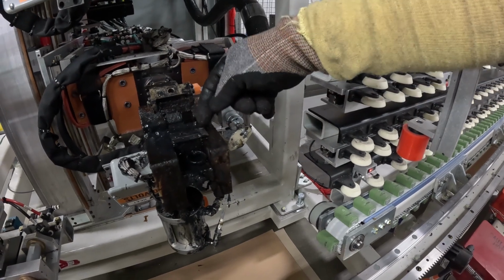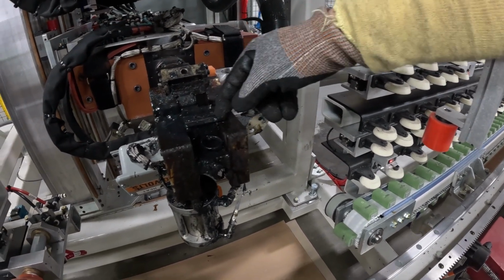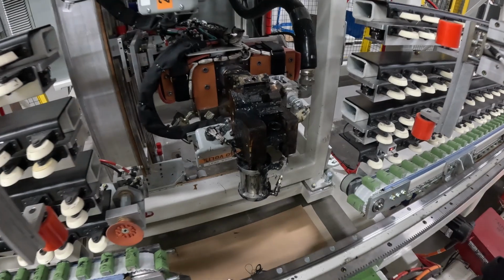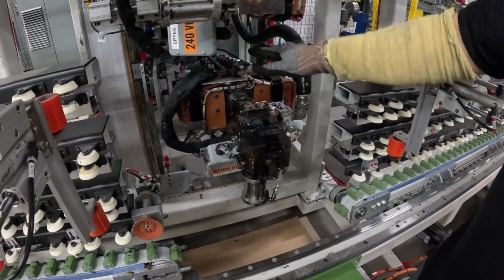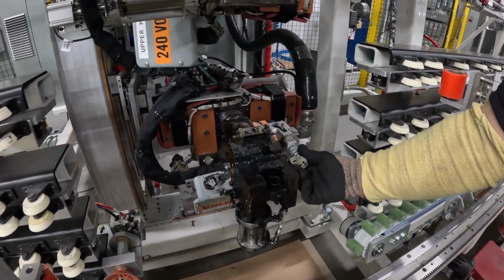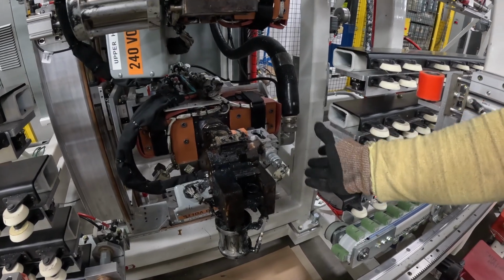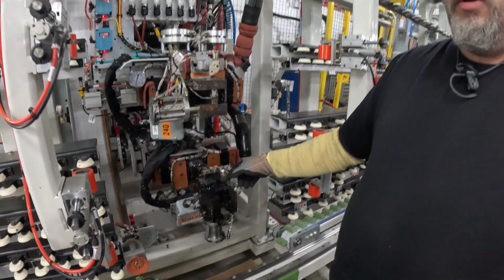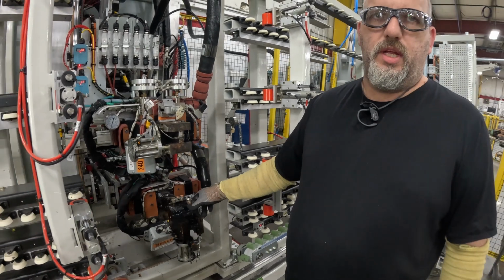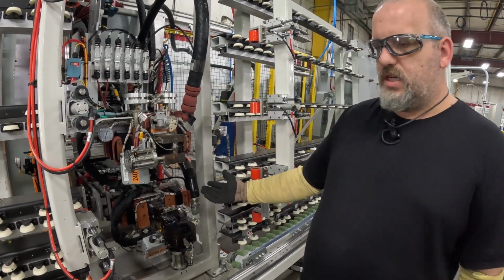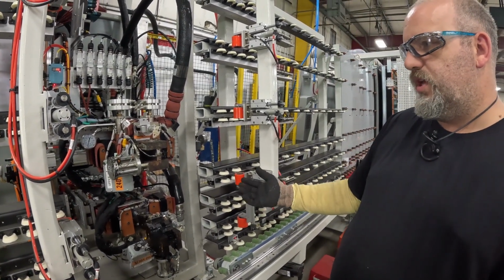The other thing, like I said, make sure your shoes are in good shape. The plastic shoes get grooves in them, which means the glass sits lower, throwing this measurement off. It won't throw it off enough throughout the course of the day, but you certainly don't want to calibrate these to worn out shoes. The steel shoes last a while—you shouldn't really have an issue with that.